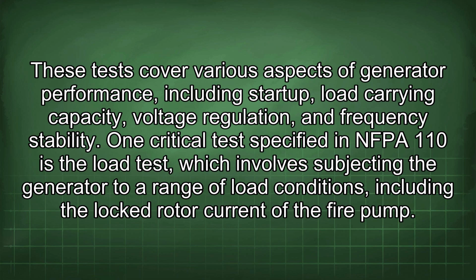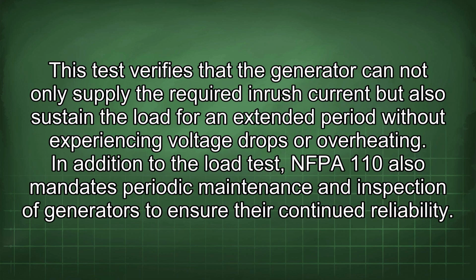One critical test specified in NFPA 110 is the load test, which involves subjecting the generator to a range of load conditions, including the locked rotor current of the fire pump. This test verifies that the generator can not only supply the required inrush current but also sustain the load for an extended period without experiencing voltage drops or overheating. In addition to the load test, NFPA 110 also mandates periodic maintenance and inspection of generators to ensure their continued reliability.